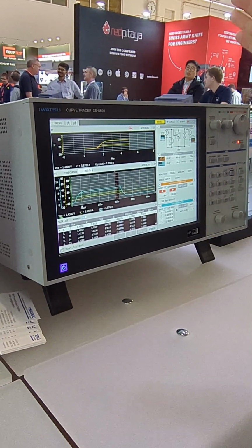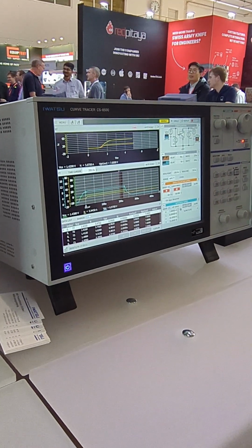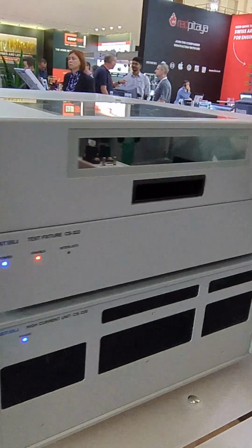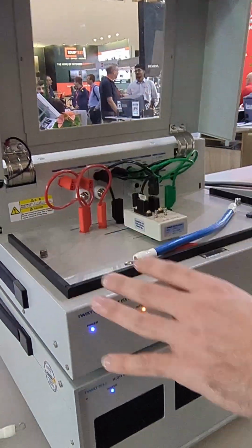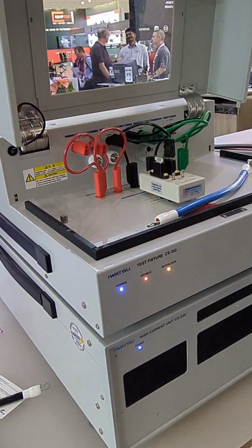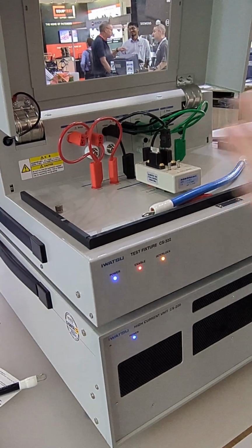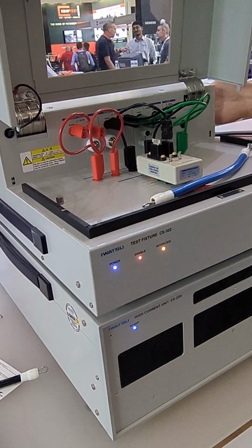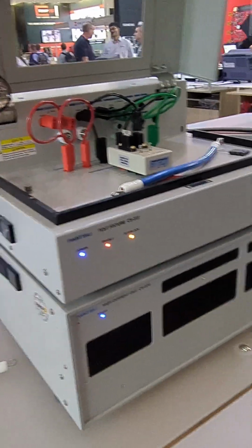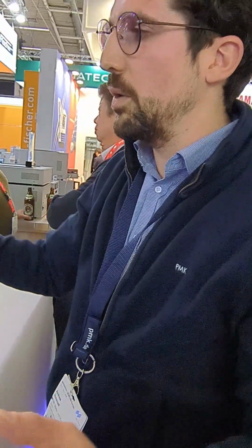And as I said, once you have this configuration, less than 2 minutes, you're done. And we also have the interlock here, and also one good thing is, once everything is cabled, you don't have to rewire. So if you switch between high voltage and current unit, the unit is doing that for you. So no rewiring needed, you just connect it and then you're ready to go.